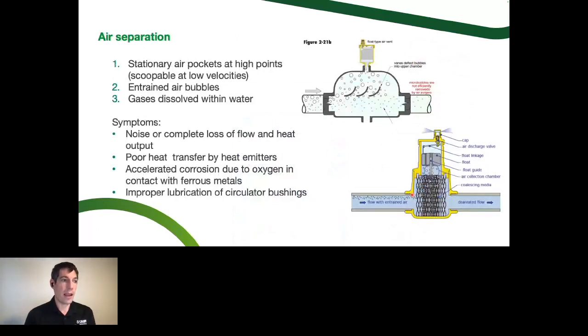So getting the air out of a system actually is three different types of air, three different categories of air that we need to get out. Something like a big air scoop like this is going to be good at getting out stationary air pockets. Like if you first turned on the water to a garden hose and you hear kind of big gulps of air coming out, something like this is going to be good at getting that big bubble of air out, bulk air. The harder ones are entrained air. So this is going to be micro bubbles that are going to look like if you poured water out of your kitchen faucet into a glass and it looks milky for a second, and then those entrained air bubbles kind of float out to the top because they're now at atmospheric pressure. That is a micro bubble that's going to be harder to catch. That's what we need this coalescing media for. Otherwise, it's just going to go straight through a device like this.